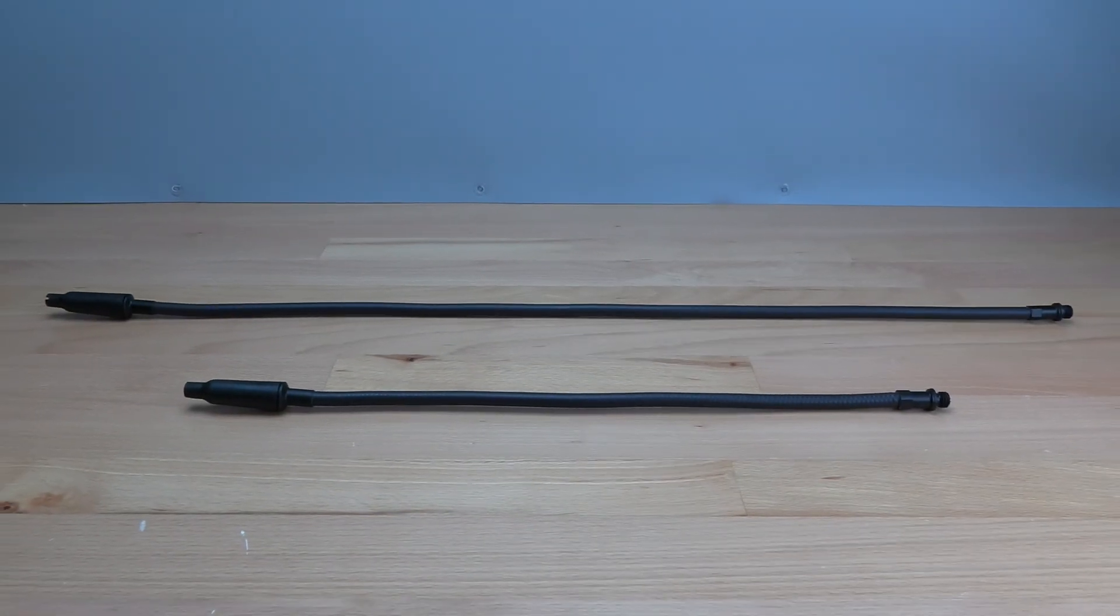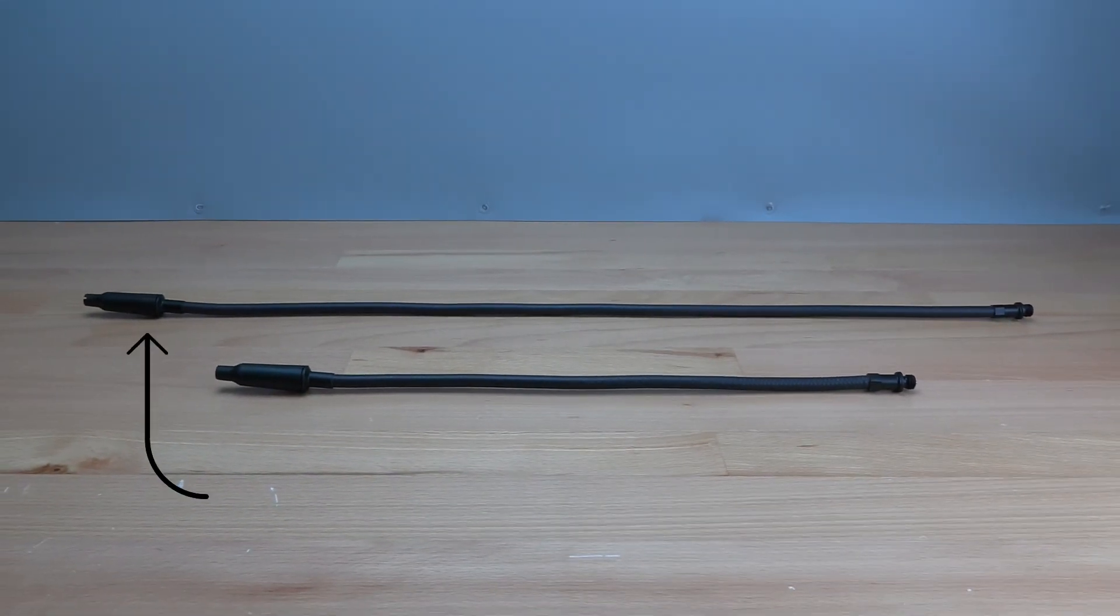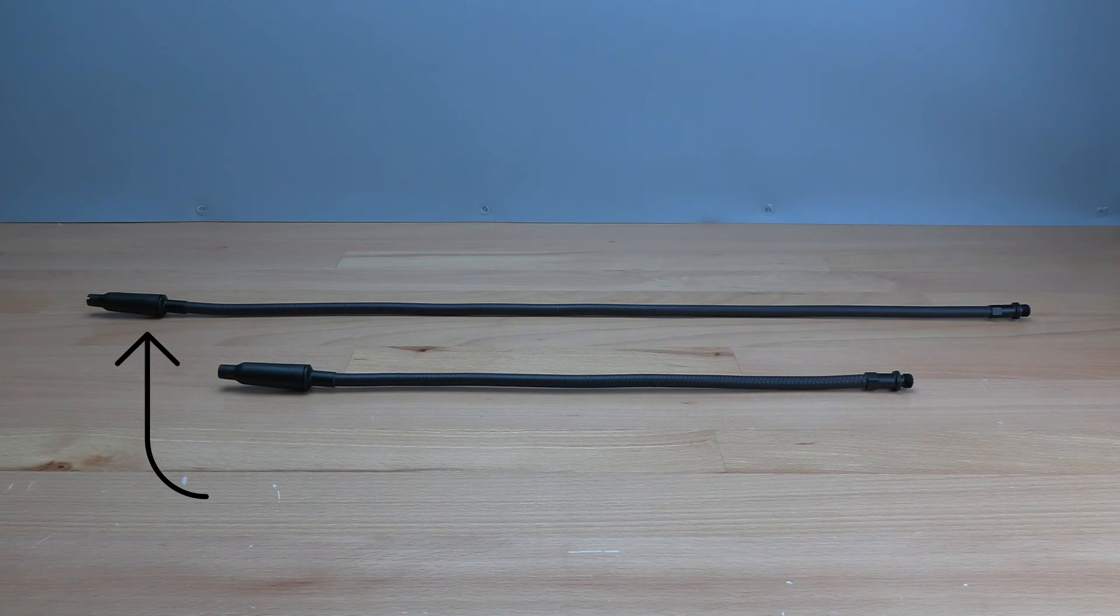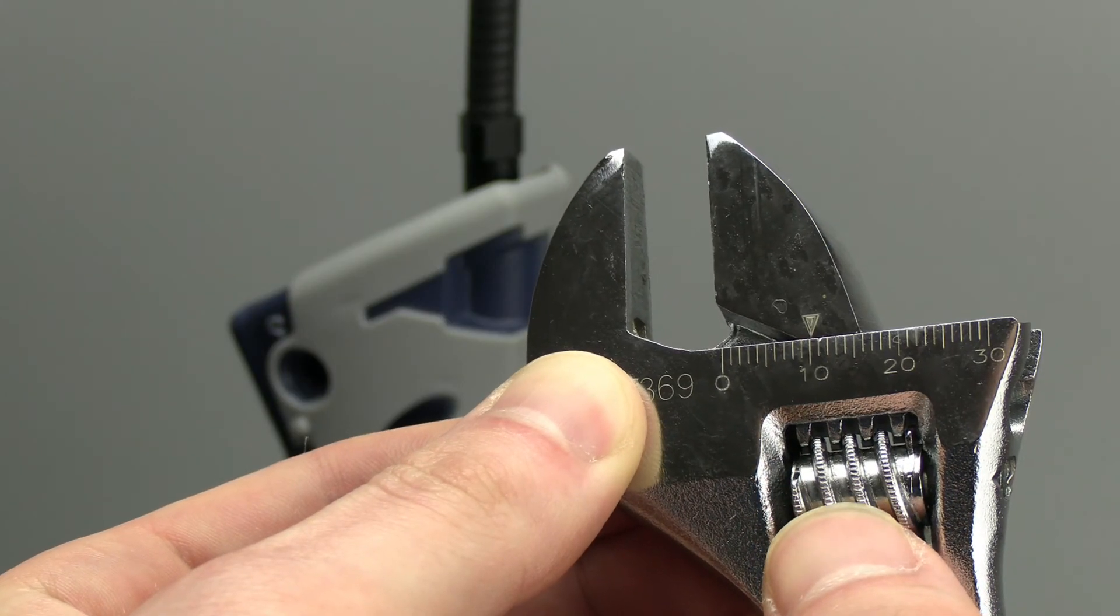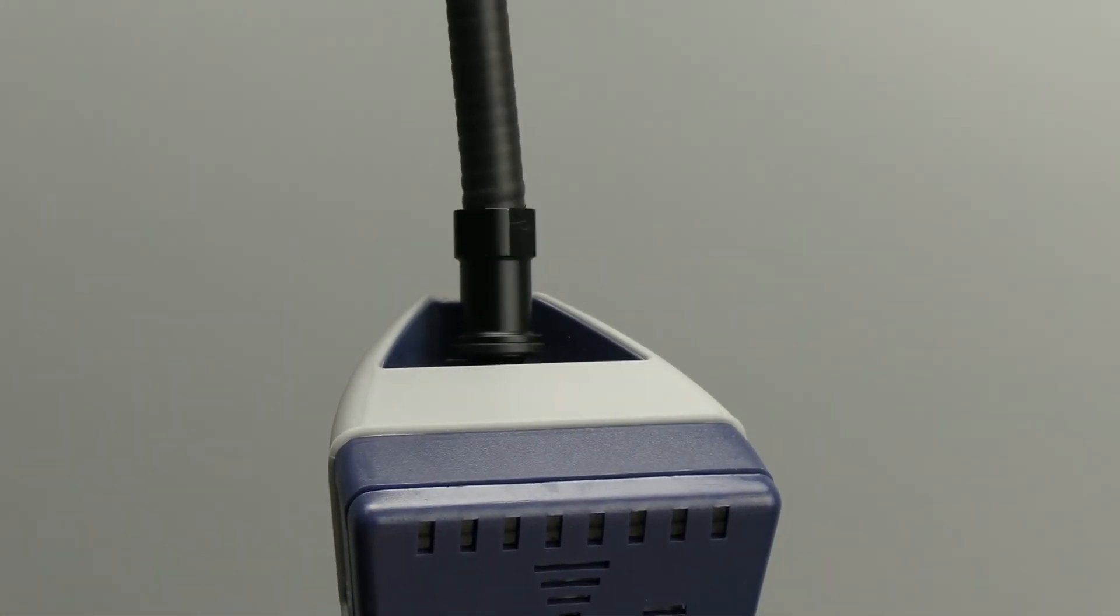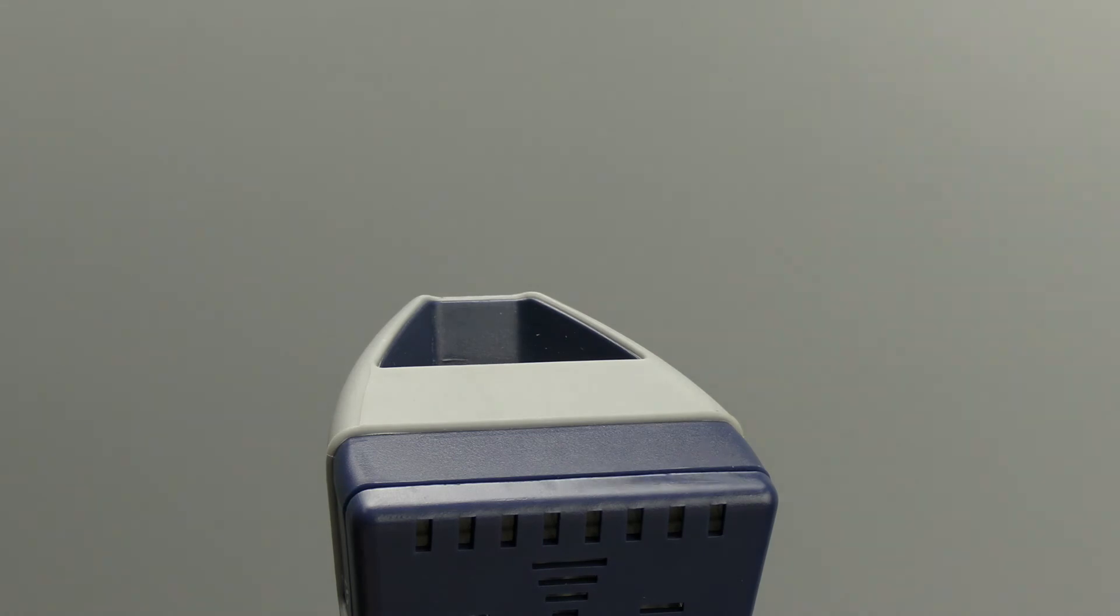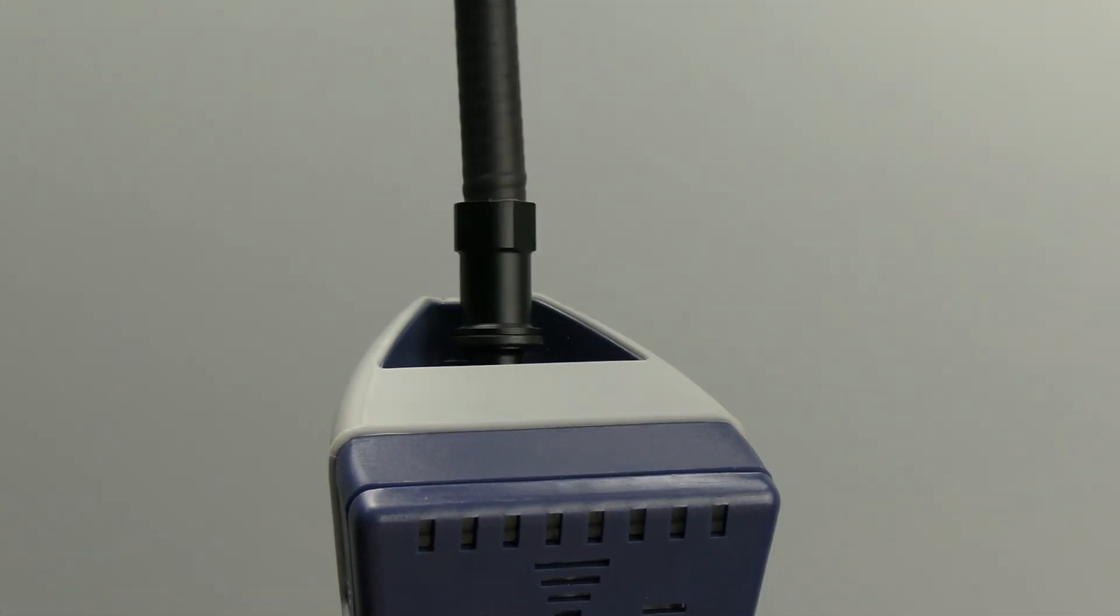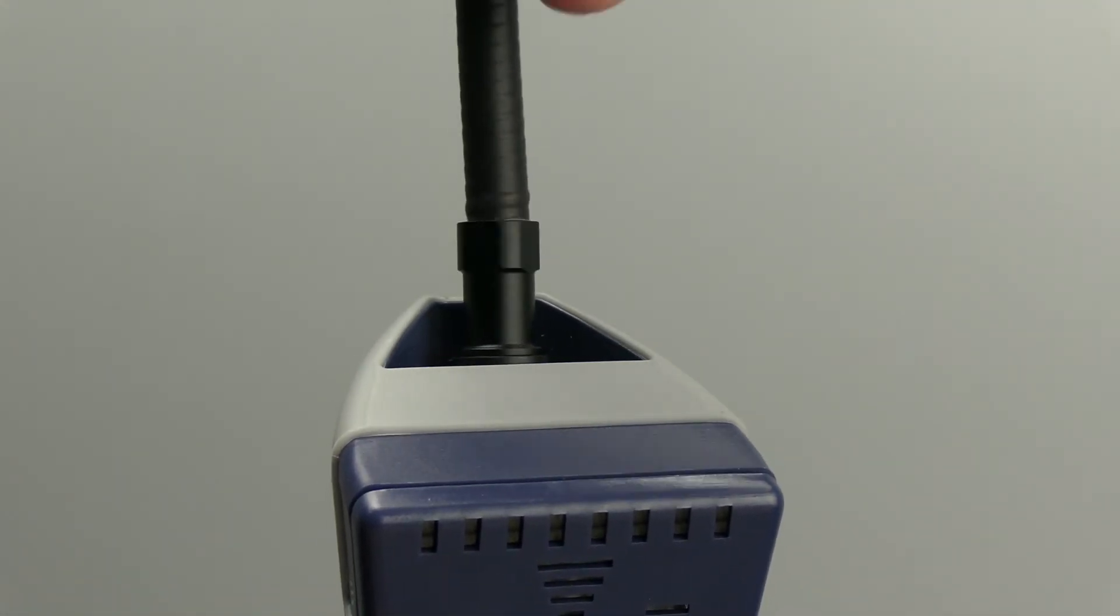The optional extra long probe can be used for those hard to reach places. To install the extra long probe, unscrew the original probe using a 10 millimeter wrench. Screw the extra long probe on and torque to about 35 inch pounds or 4 newton meters. Torque doesn't have to be exact, just make sure you don't over tighten it.